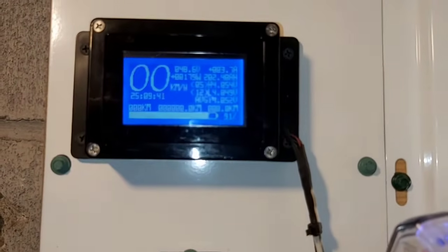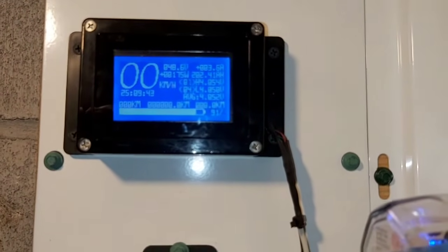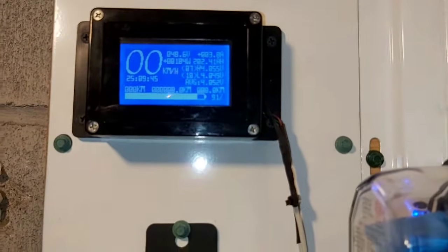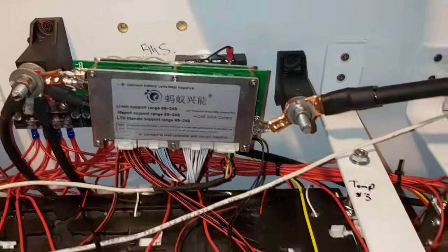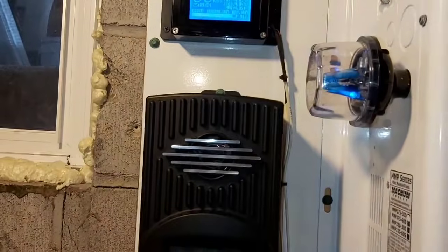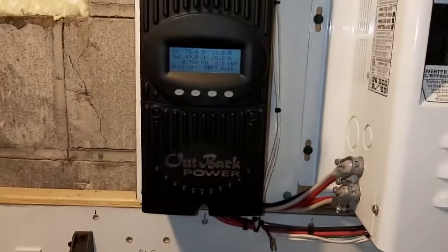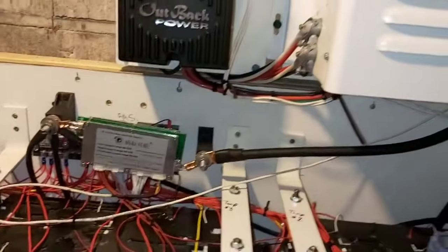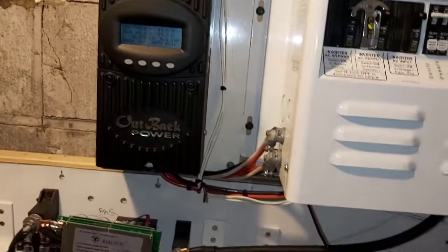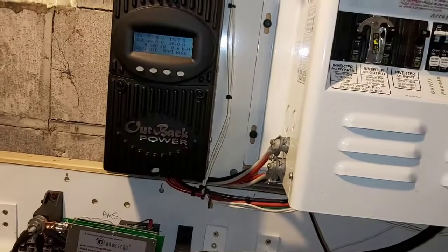We're at 0.6 and now we're at 0.5. So when it hits 0.6, it starts balancing between the high and the low. So we're only 0.4, 0.5, 0.6 there. Now we're balancing and then it stops. So it is kind of keeping everything in check too, and we're only getting 3 amps going to the battery, so a little bit of balancing will smooth it out. If it gets too far out, it will automatically balance at night or something like that.